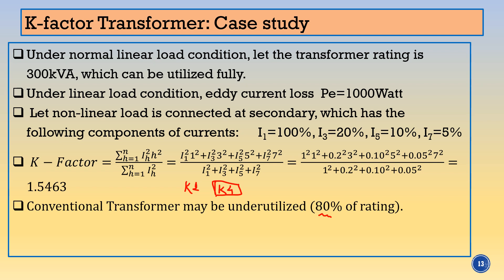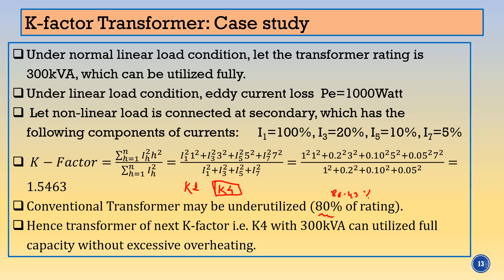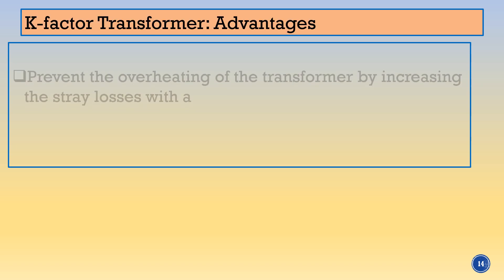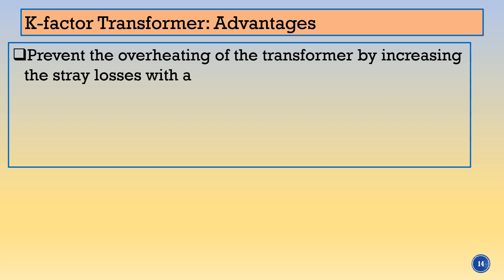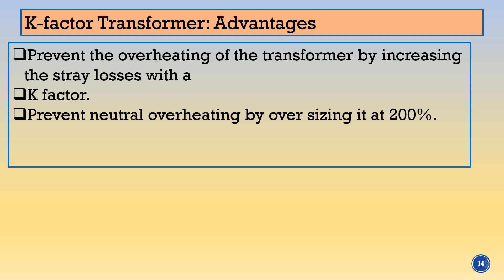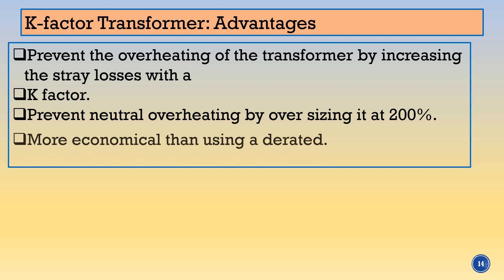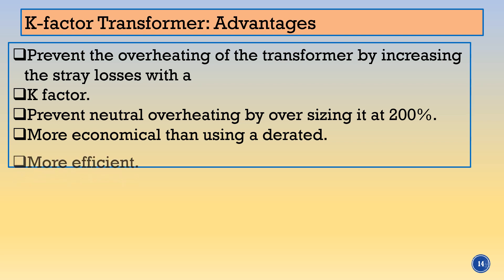If we use the conventional transformer, as seen in the previous example, only 80.43% capacity can be used. But if we use the K4 type, then the full 300 kVA capacity can be utilized — the transformer can be utilized up to 300 kVA without excessive overheating. That is the main advantage. If we load a normal transformer beyond 80%, overheating may occur and the transformer life is sacrificed. Using the K rated transformer, we can utilize it fully.